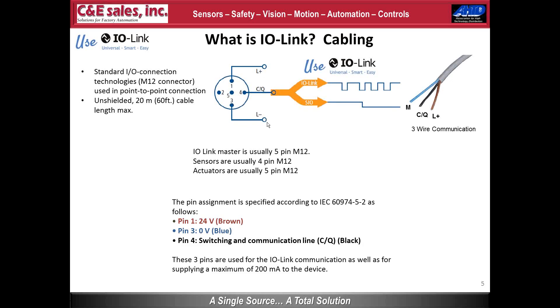Q&A session: Did you mention the cable length limitation? The maximum cable length between the master and the device is 20 meters. Taking precautions and using shielded cable is recommended, although the standard says it is not required.